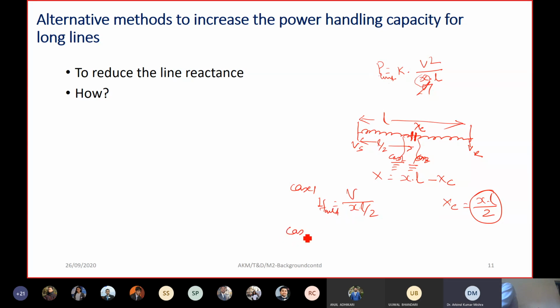For case 2, the fault current is V upon XL by 2 minus XC. Unfortunately, if we choose this XC as XL by 2, half of the reactance as in the previous example, this quantity becomes 0, and the fault current ideally becomes infinity. In fact, it will be limited by some resistance of the line, so it will not be infinity, but it will be very high.